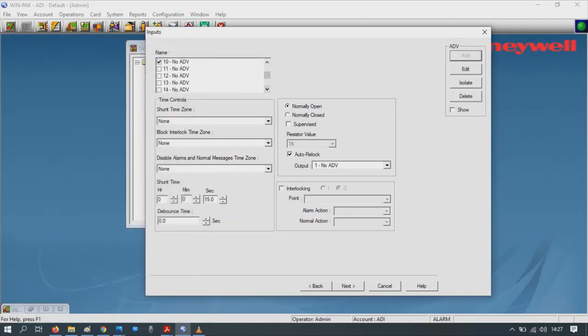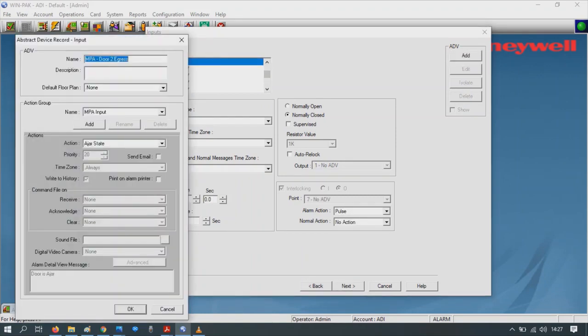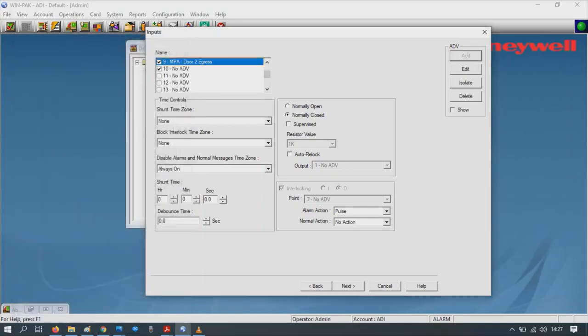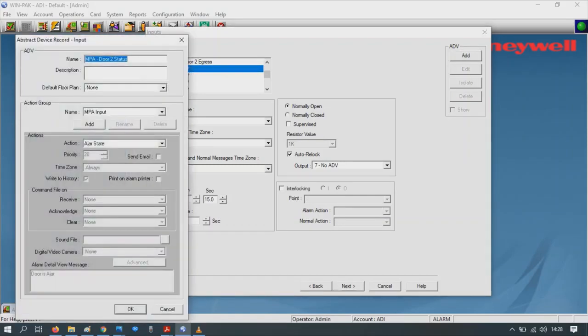Door 2, Add. Same as before. You'll notice I'm changing the inputs from normally closed to normally open, so for the exit buttons normally open. For door status it can be normally closed or normally open, depends on your door contact or if you're using a door contact. Once you're finished, press OK.